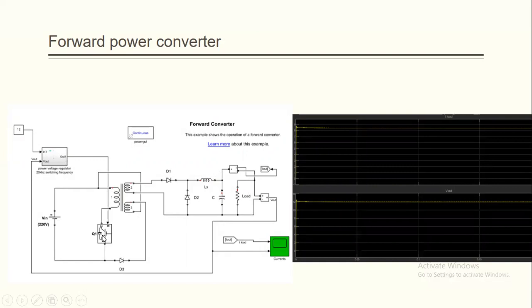The MOSFET, or in this case the IGBT, is controlled by a power voltage regulator. We have two inputs for this power voltage regulator: the desired voltage output we want, and the closed loop from the voltage measurement in order to calculate the difference between them.